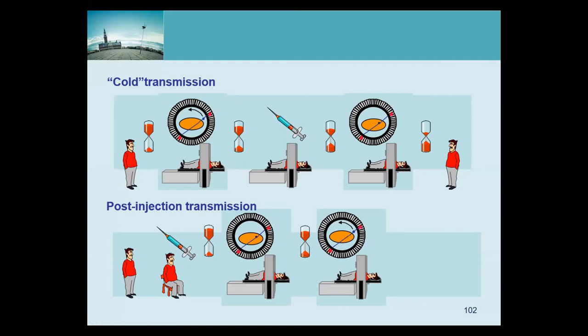In PET-CT, we do it the other way around — scan the entire patient with CT and then do bed-by-bed acquisition. That means for the last bed position, there was a long time between when the CT image was made and when we measure the activity, and the chances that the patient moved in between are pretty high. With the old transmission approach, motion mismatches were less likely to occur, and if they did occur, they were more local. This was relatively practical, extending the scan by just a few minutes.